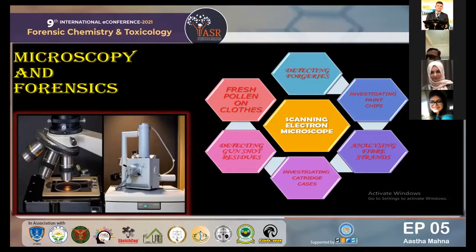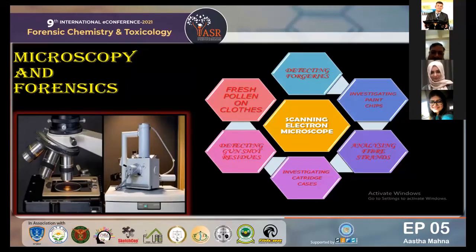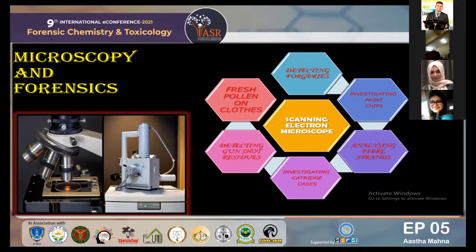The main problem with imaging uncoated paper surfaces is the charging effect. Paper is non-conductive and therefore, in the past, it was coated with a metal layer to eliminate charging at high kV. After coating, written lines can only be imaged if the imprint has changed the topography of the paper. Today, instead of using high kV for imaging, an extremely low voltage of 0.7 to 2.0 kV is used, allowing imaging to detect the topography of paper in its natural state. Forensic SEM is ideal for investigating uncoated paper. In combination with different imaging possibilities such as SE and BSE signals, together with signal mixing and image processing techniques, the SEM allows the solution of intersection problems to trace and identify forgeries in documentation.